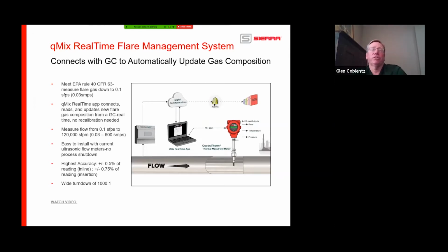Now, one of the advancements that we've had with Q-mix, taking it up to the next level, is the Q-mix real-time flare management system. This is where you can combine a 640i with Q-mix and a gas analyzer hooking to a laptop, which ends up being an industrial laptop in the field, or an industrial PLC, where this is running constantly, and you can upload new gas compositions into the meter as often as once a minute if you want to.